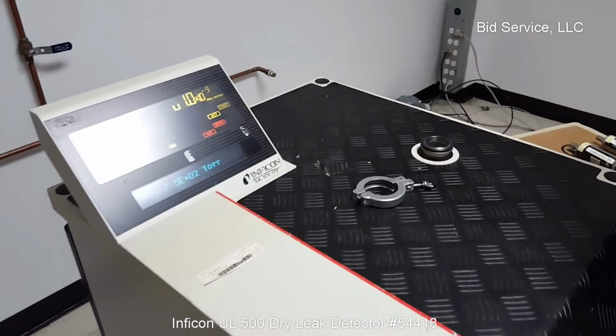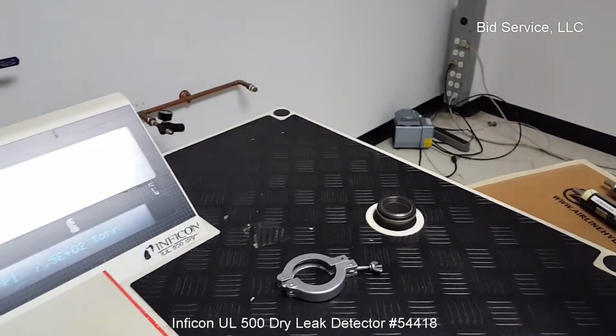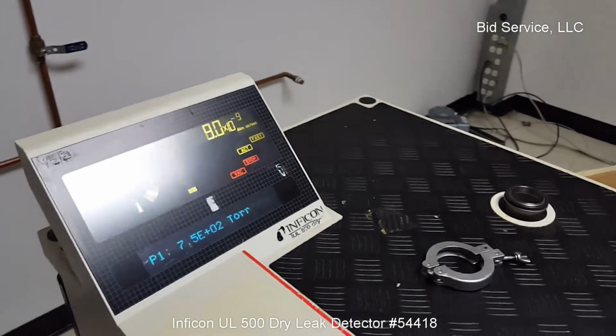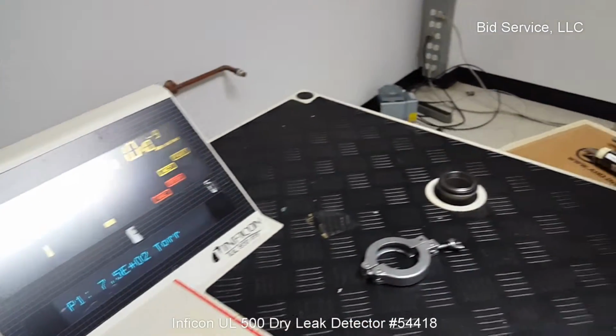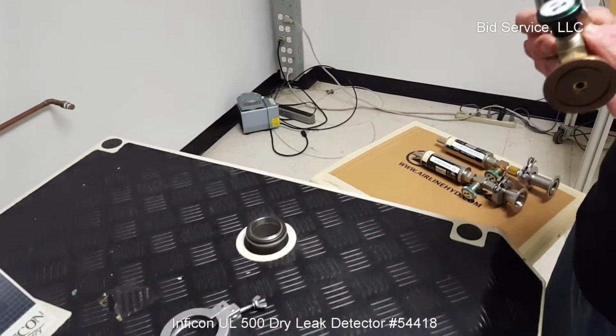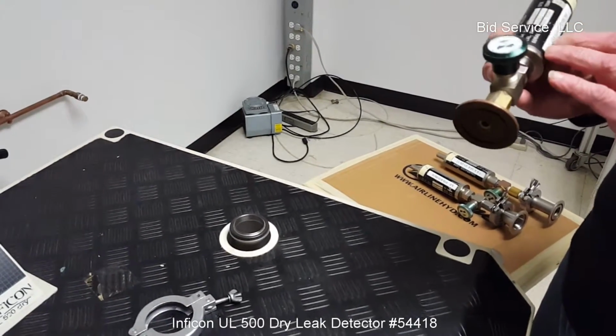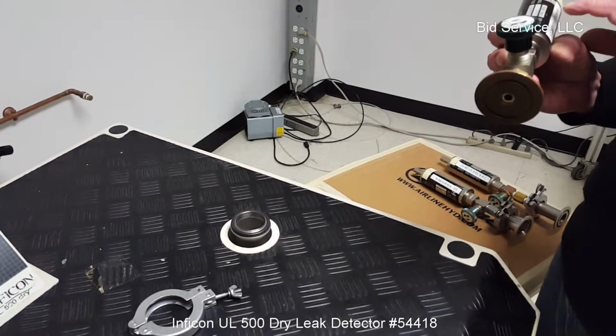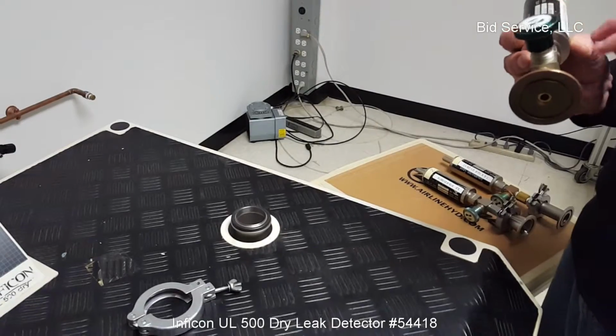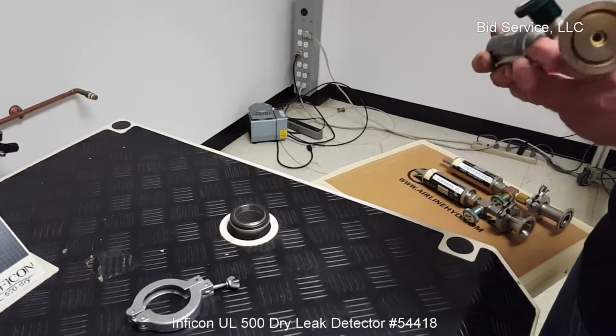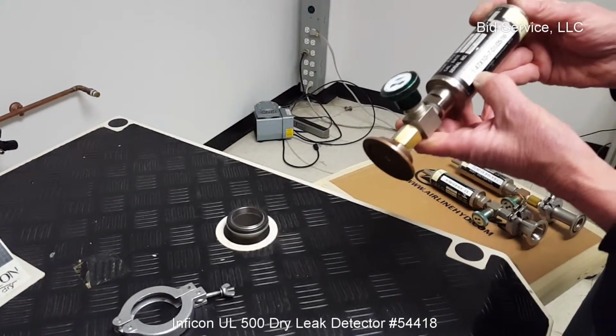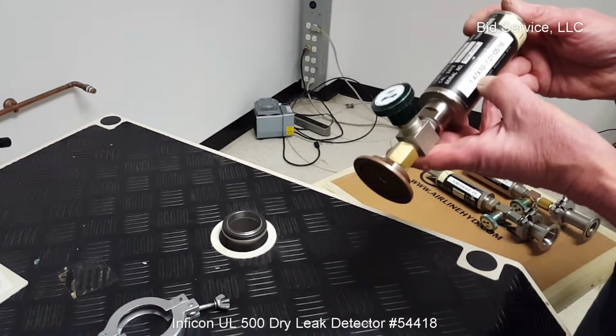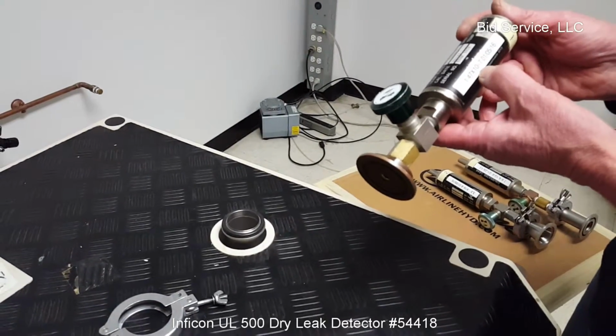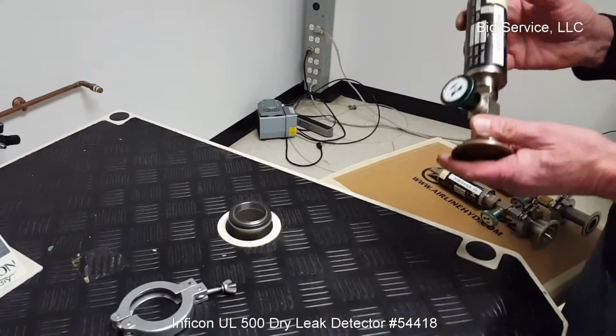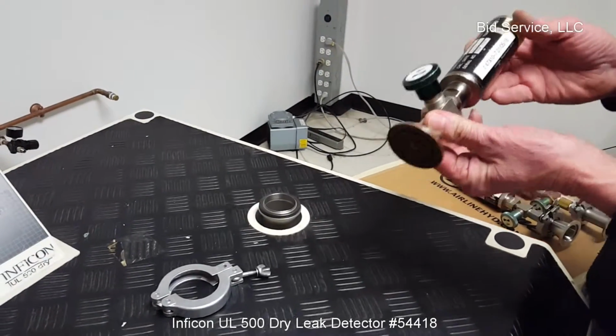We have 3 different calibrated leak sources. These helium leak sources are annually recalibrated to reflect the amount of helium that's depleted over an amount of time. This particular unit has been calibrated to 1.47 times 10 to the minus 7th. I personally did this recently in January. We'll use this one first.